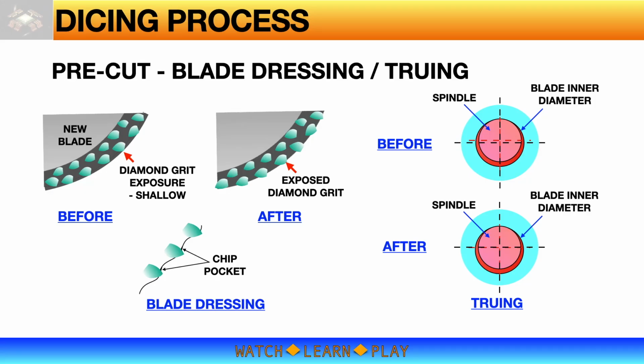A new blade is immediately ready for use to cut a wafer. However, while it is good to use, it is actually not at optimum condition for best cutting quality. The reason is the exposure of diamond grits on a new blade is shallow and may be uneven. Blade dressing is the process of uniformly exposing the diamond grits. This is done using a dressing board or plate, cutting at a very slow speed for a certain number of cuts.